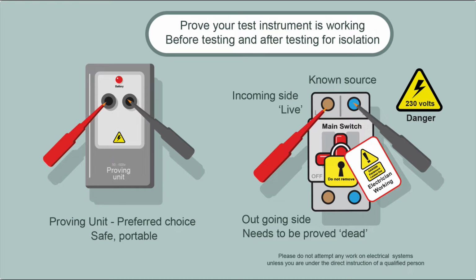Your voltage tester is so important, but we need to verify that it actually does work every time we carry out safe isolation, before we test and after we finish testing. The preferred method to prove your voltage tester is to use a proving unit because it's safe and it's portable, you can carry it around with you. It's got 2 connection points that you put your probes into and it'll simulate the voltage, 230 volts or whatever.